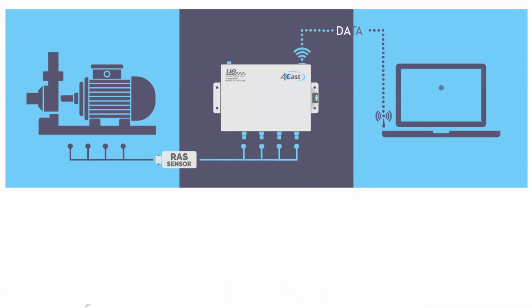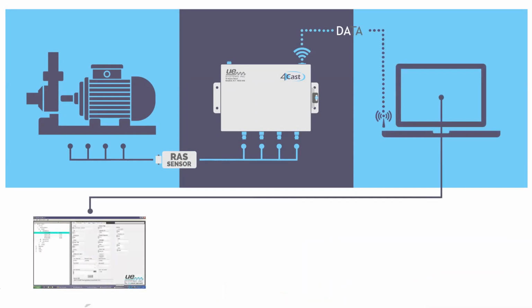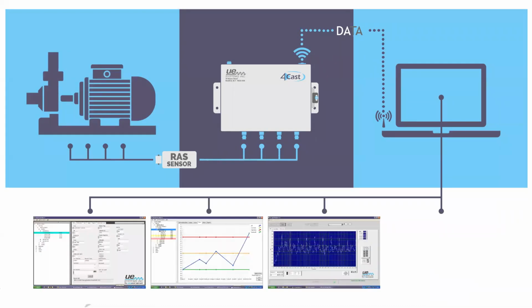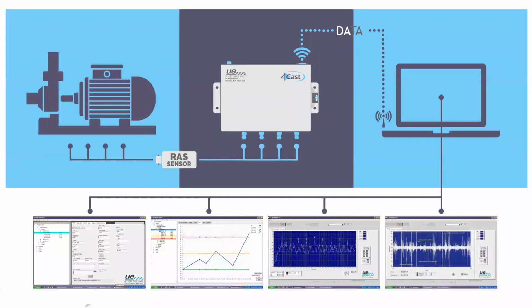And then with that, it will monitor our bearings 24/7. We can set alarm levels, we can set baselines, and we can then also get readings sent to us on a periodic basis, just so we know that we're actually getting good sounds and good readings. And then when it does hit alarm levels, we can also have it notify us via email, via the software, or via chat groups even as well.